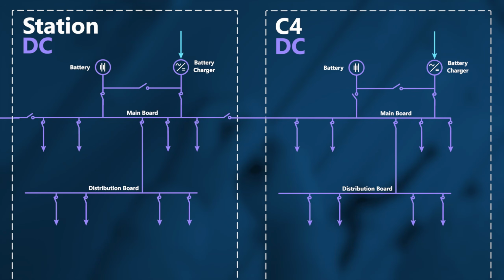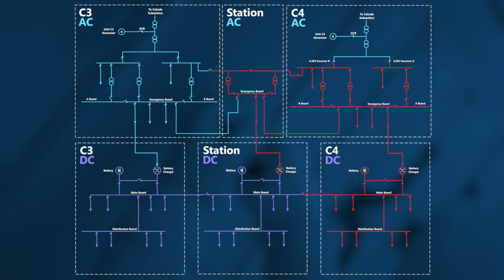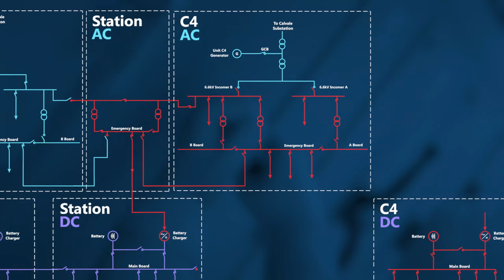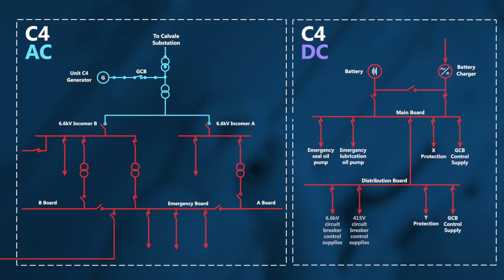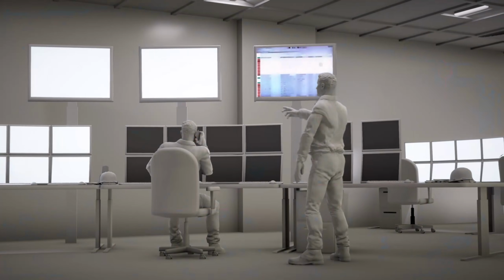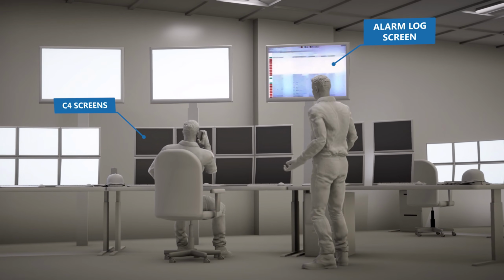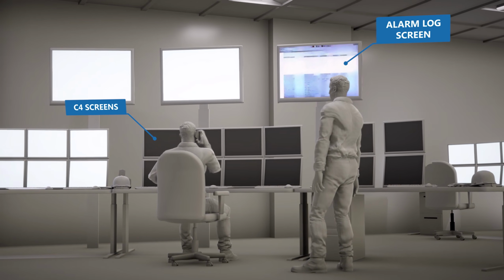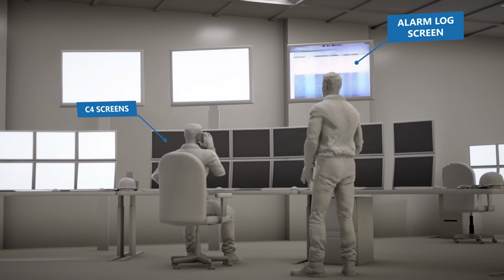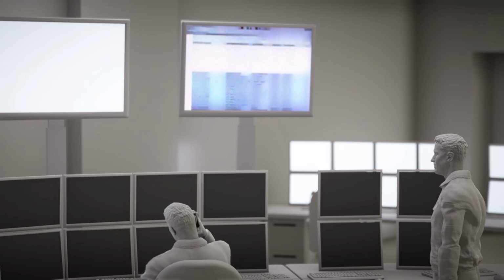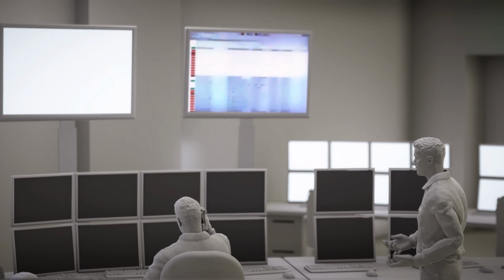The opening of the interconnector initiated an almost instantaneous loss of DC power and AC power to the unit. Without power, the turbine generator had lost critical primary and emergency lube oil and seal oil pumps, but it was still connected to the grid. Without protection, the unit could not be disconnected, nor could it be shut down safely. And without power to their screens, the operators in the control room had no visibility or control of Unit C4, and no way of telling that the plant was on a trajectory towards catastrophic failure.